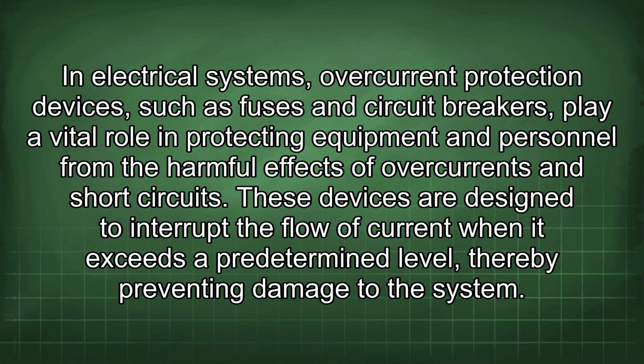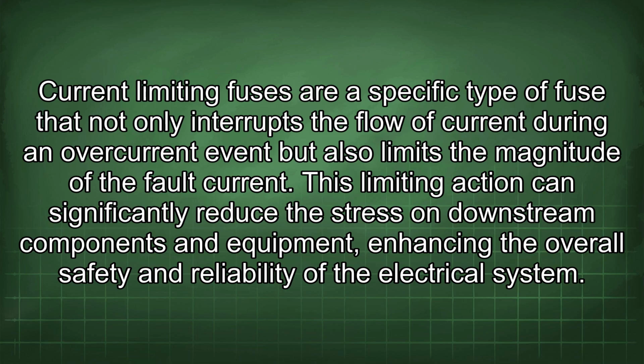In electrical systems, overcurrent protection devices such as fuses and circuit breakers play a vital role in protecting equipment and personnel from the harmful effects of overcurrents and short circuits. These devices are designed to interrupt the flow of current when it exceeds a predetermined level, thereby preventing damage to the system. Current-limiting fuses are a specific type of fuse that not only interrupts the flow of current during an overcurrent event, but also limits the magnitude of the fault current.